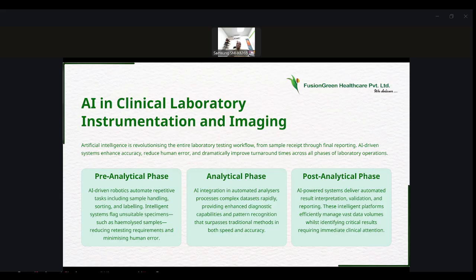The pneumatic system will collect all the samples and send them to the pre-analytical area, the sorting area. In this pre-analytical area, we have the pre-analytical systems, which will be connected with the TLA, total lab automation systems. This pre-analytical system will take care of sample handling, like sorting the samples depending upon the instrument and the different departments, and it will sort and relabel if needed, even if the sample is going to a different instrument or different department. With intelligent flags, unsuitable specimens such as hemolyzed samples are detected.